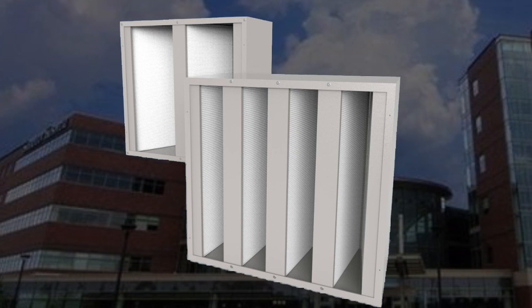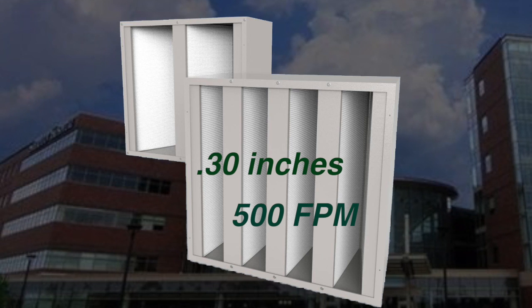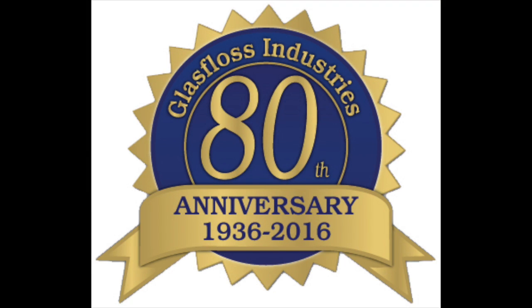The PureCell V MERV 14 filter's initial resistance of 0.3 inches at 500 feet per minute allows for energy savings and extended filter life. Glasfloss Industries is the oldest American independently owned and operated manufacturer of HVAC filtration products and is a clear choice since 1936.